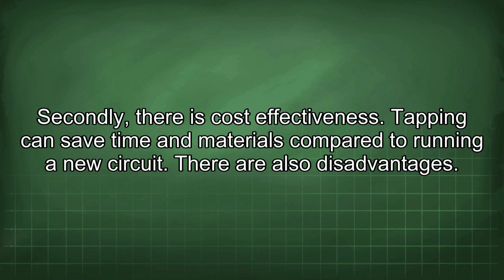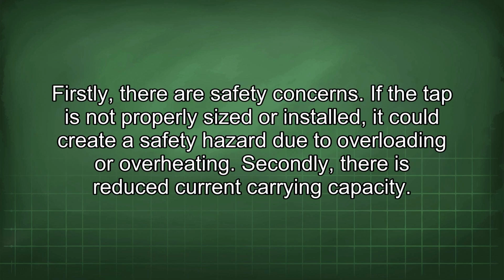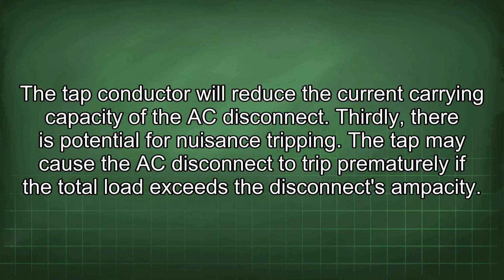There are also disadvantages. Firstly, there are safety concerns. If the tap is not properly sized or installed, it could create a safety hazard due to overloading or overheating. Secondly, there is reduced current carrying capacity. The tap conductor will reduce the current carrying capacity of the AC disconnect. Thirdly, there is potential for nuisance tripping. The tap may cause the AC disconnect to trip prematurely if the total load exceeds the disconnect's ampacity.